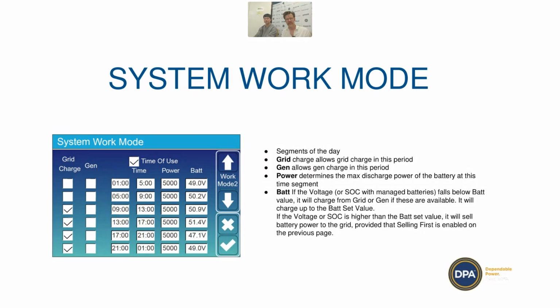If we ticked grid charge here, then it would be allowed to charge the batteries from the grid in this time section. And it would only charge them if the voltage got below 49. And if the voltage got below 49, it would charge them back up to 49, and it wouldn't charge them over that. And it would do it, according to this column here, power, it would do it at 5,000 watts.